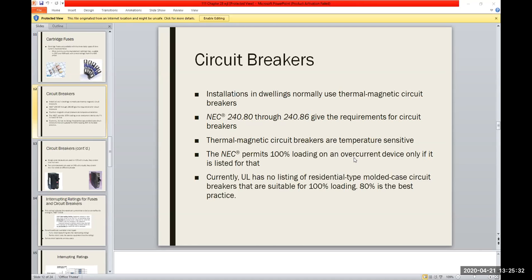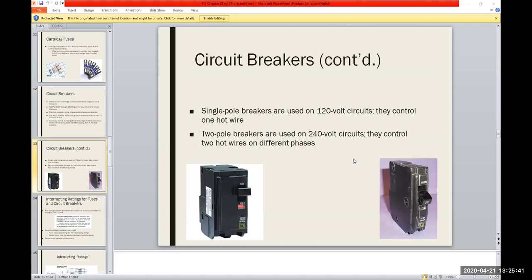So in most cases, you never really want to go for anything where you get 100% loading. Usually you get to a certain point and have it trip at that point. We use two styles typically that you'll see in your panel. You'll get the single, right? That's the one on the right-hand side where it's just a 120. You have one line attached to it. And then you get the duals, which are for 240-volt circuits. These will generally be set, but they do come in 20 amp sizes as well. Generally, you'll see them in the higher ranges, the 30s, the 50s, the 70s, that type of thing. And you'll have two lines coming into that, so two hots.